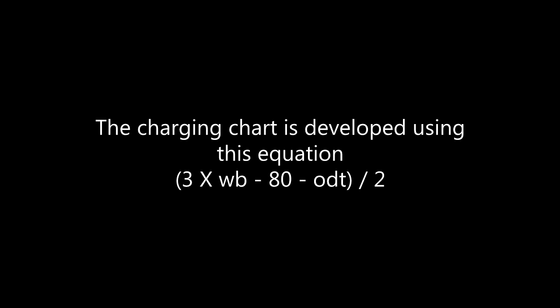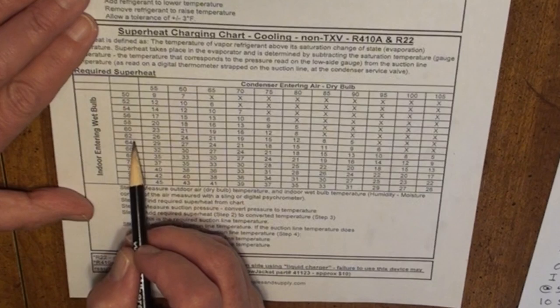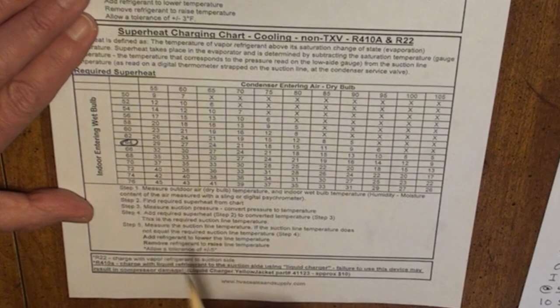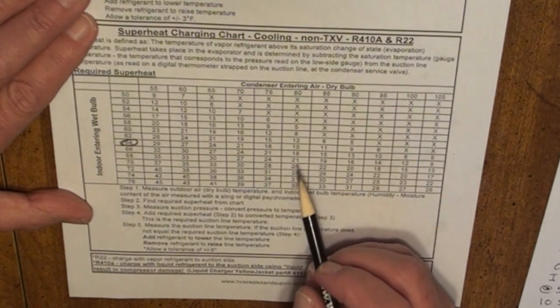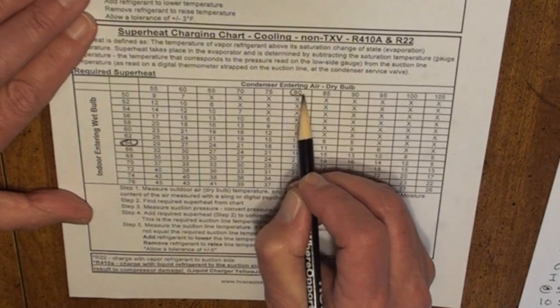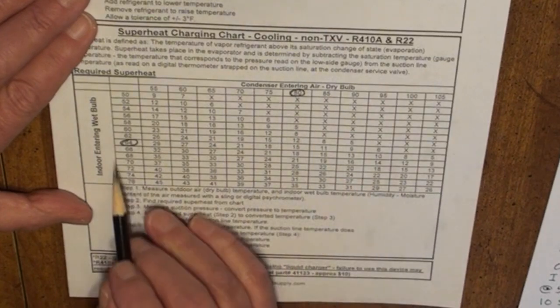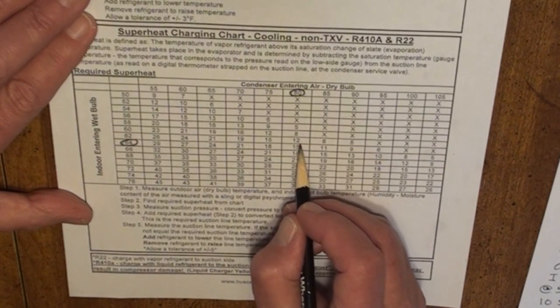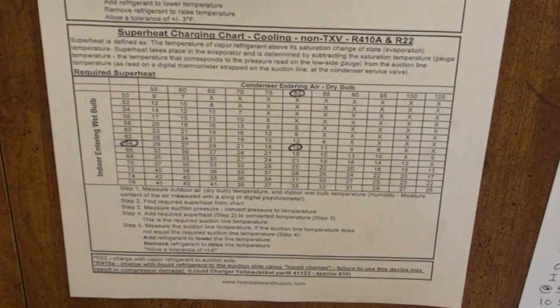For example: if we have 64 degrees entering wet bulb temperature at the evaporator return and an outdoor temperature of 80 degrees, we would expect a measured superheat of 15 degrees. As the conditions vary, the superheat reading will also vary.